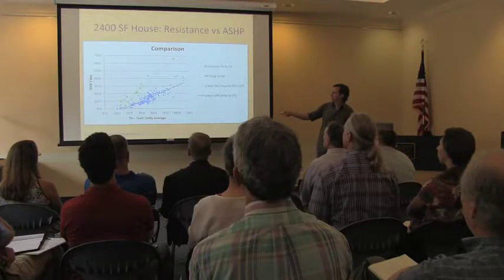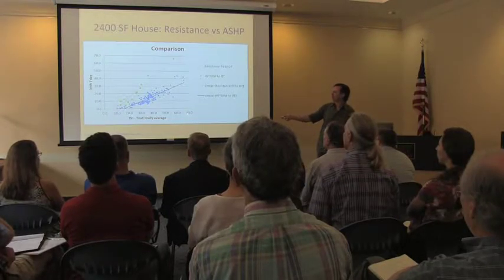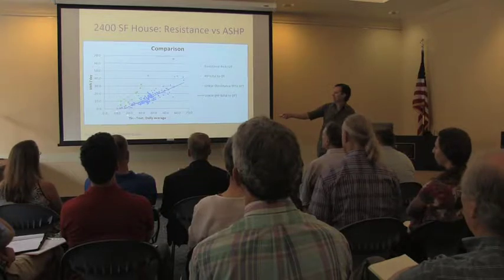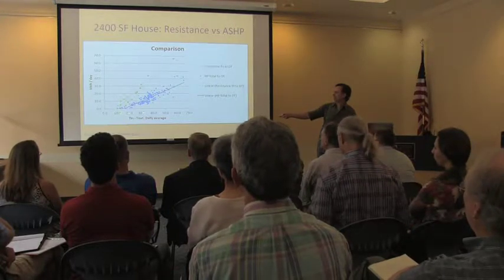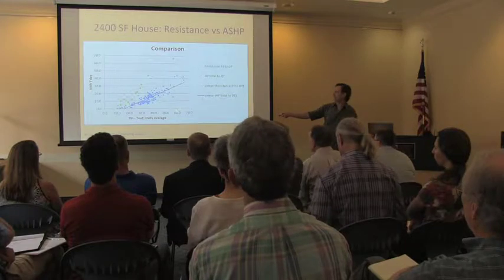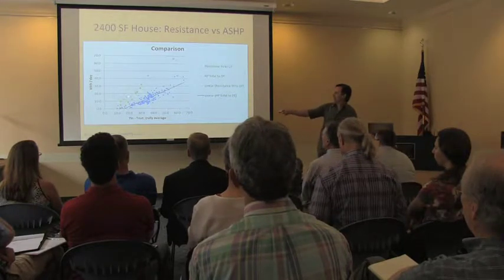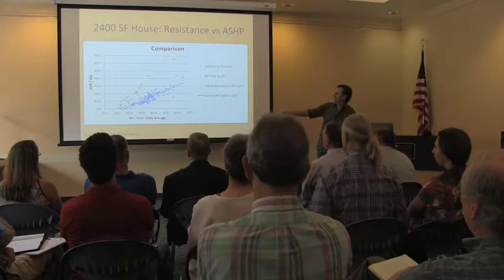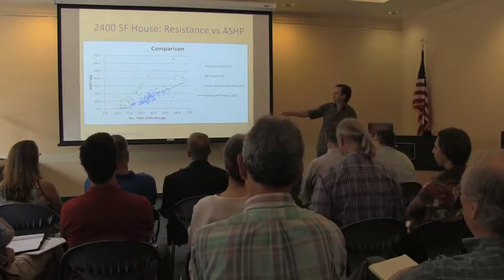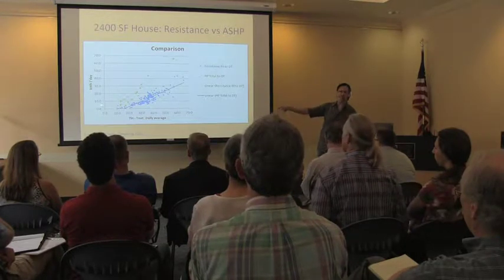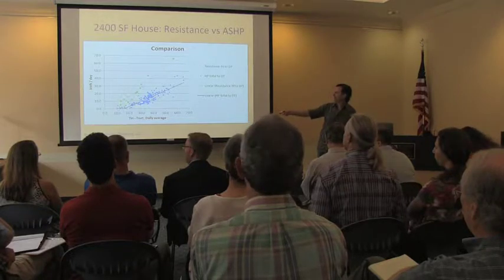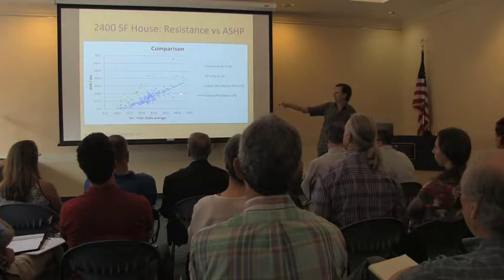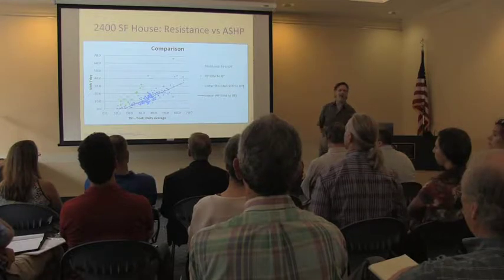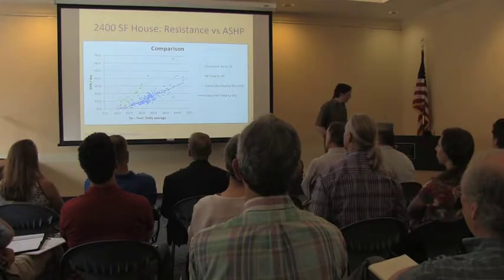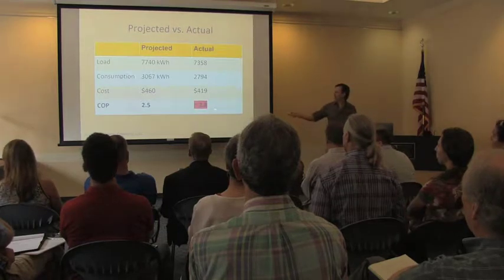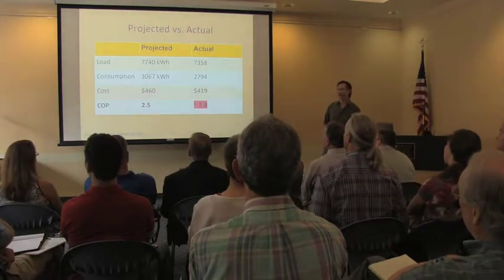So I got a baseline of what's the actual heating load under different indoor-outdoor temperature differences. So this is like 50 degrees outside, and that's like 0 degrees outside, or minus 10. And so these were the daily average temperatures with the electric heat, and this is the amount of energy it took per day to heat the house. And then these were the data points running that heat pump for that same winter for all the days that I ran the heat pump exclusively. And it's essentially almost a 3-to-1 difference. So my net efficiency is a little less than 300%.